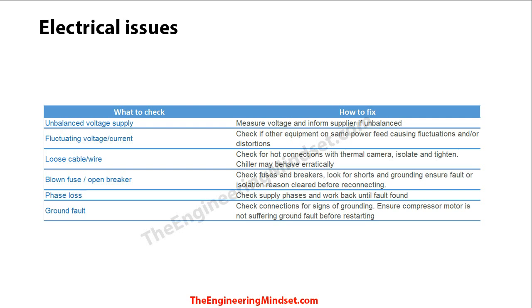Another fairly common cause is a blown fuse or open breaker — check the fuses and breakers on your LV panels. Before resetting any breaker, check for grounding faults and ensure no one is working on the machine. Make sure the equipment has not been isolated for safety reasons, and speak with your authorized person before turning anything back on.